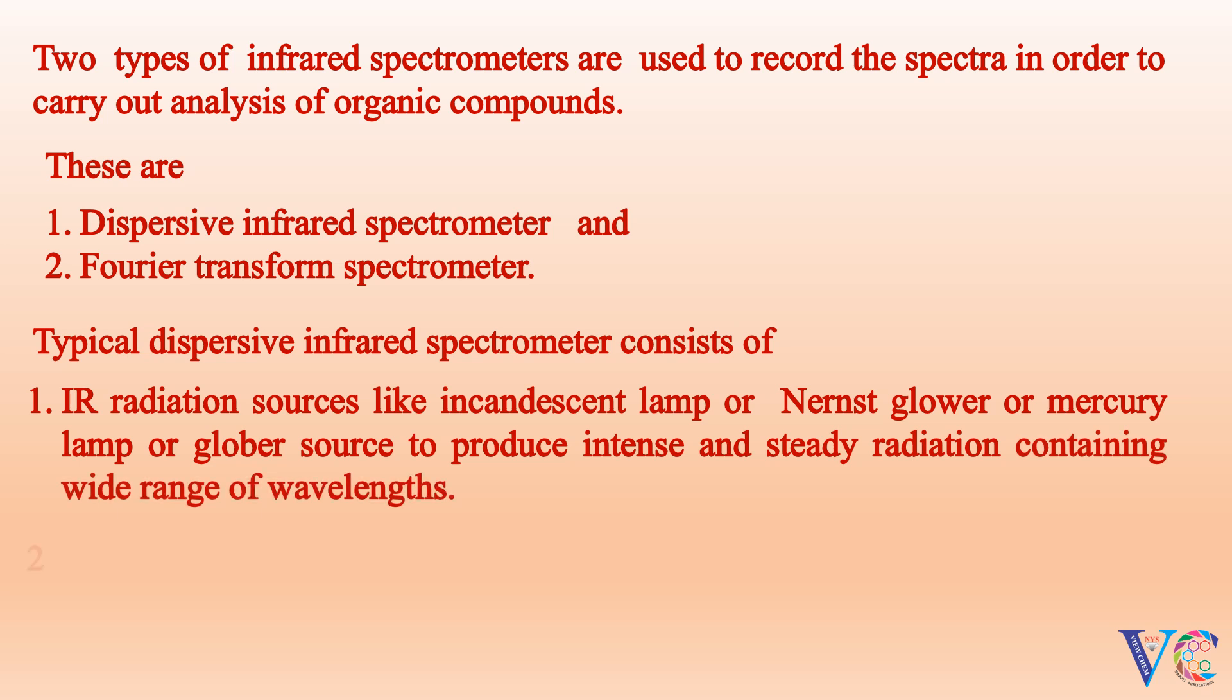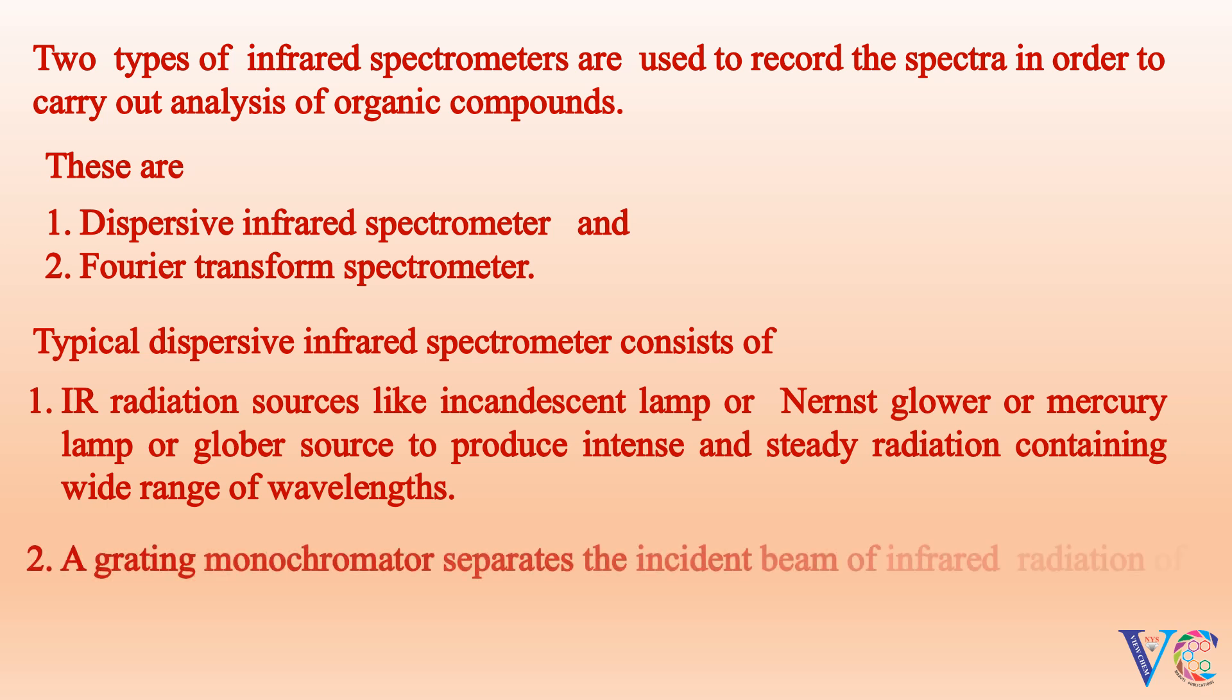A grating monochromator separates the incident beam of infrared radiation of different frequencies by dispersion.